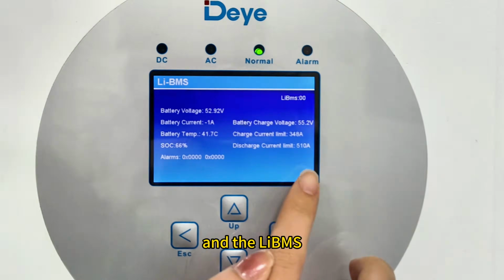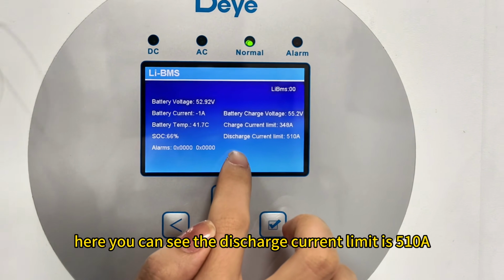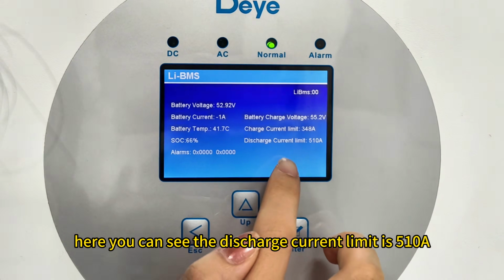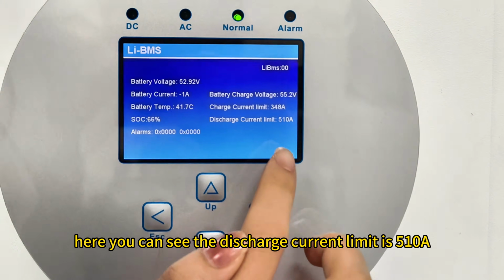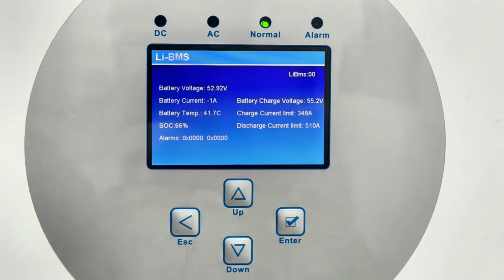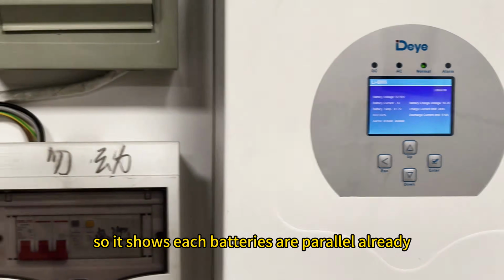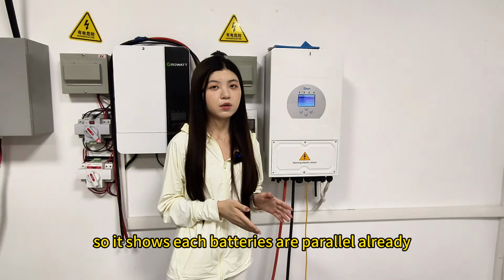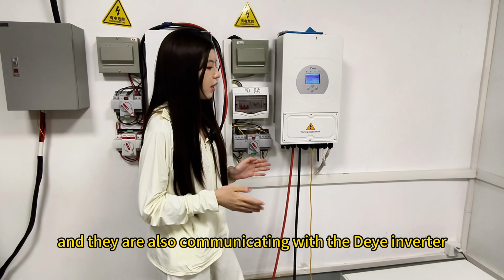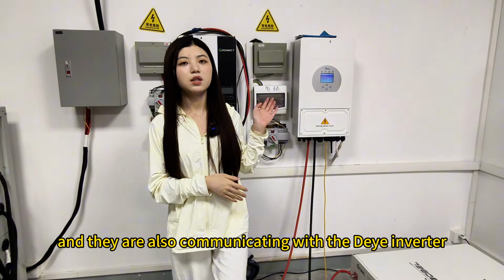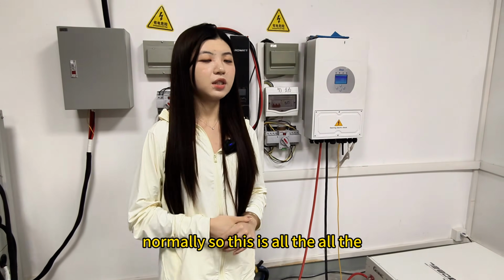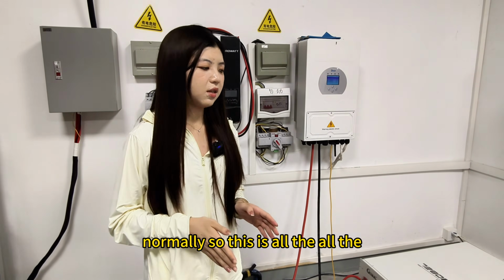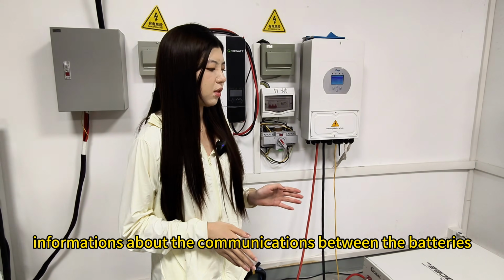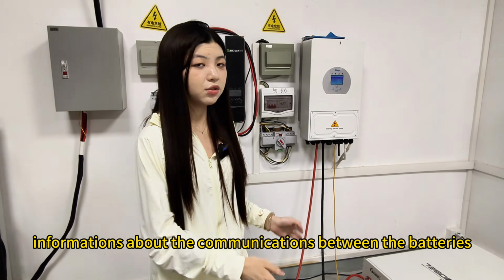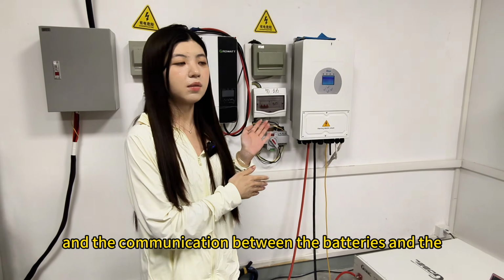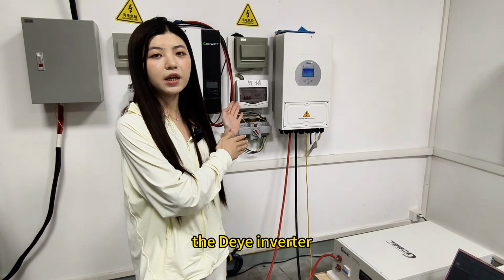And the lithium BMS, here you can see the discharge current limit is 510 amperes. So it shows each battery is already paralleled, and they are also communicating with the inverter normally. So this is all the information about the communication between the batteries, and between the batteries and the inverter.